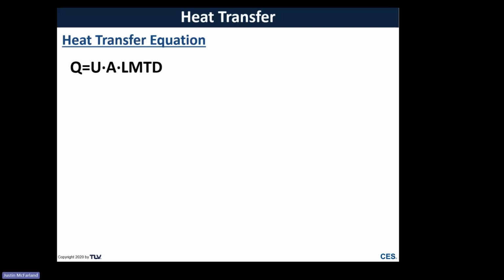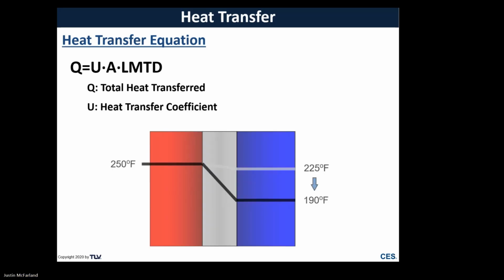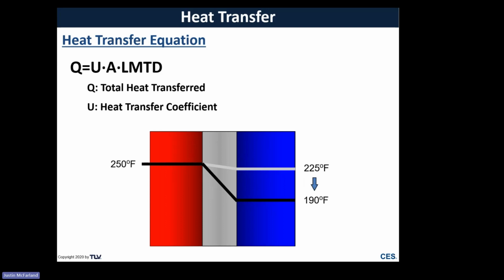And so with those in mind, I'm going to go through the heat transfer equation. So if anybody is an engineer, maybe you've seen this at some point in your studies. If you're not, I apologize, but I'll go through this quickly and try to explain everything. So heat transfer equation, Q equals U times A times LMTD. So Q is our heat transfer, it's the total heat. U is the heat transfer coefficient. And so that really relates to how easy heat transfers from the hot side, and in case we're talking about here steam, as it passes BTUs through some sort of heat boundary, usually some sort of steel surface, and then into the cold fluid that needs to be heated up.